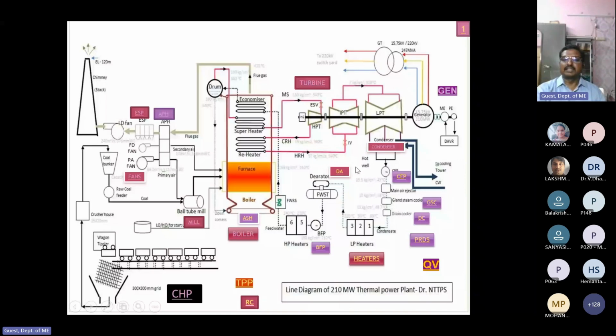The next one in the turbine circuit is the CEP. This is called a condensate extraction pump, because a normal pump cannot extract the water: the condensate is at a very low pressure because of the vacuum. So this is the CEP, a special pump with 7 stages. It will extract water from the hot well. The bottom part is called the hot well. The water collected from the condenser is collected in the hot well.